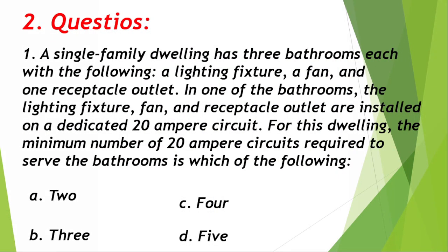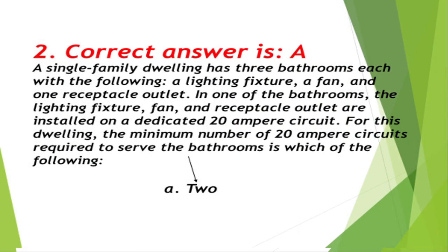Question number 2: A single family dwelling has three bathrooms, each with a lighting fixture, a fan, and one receptacle outlet. In one of the bathrooms, the lighting fixture, fan, and receptacle outlet are installed on a dedicated 20-ampere circuit. The minimum number of 20-ampere circuits required to serve the bathrooms is: A. 2, B. 3, C. 4, D. 5. Correct answer is A, 2.